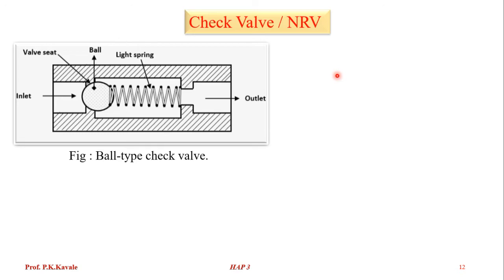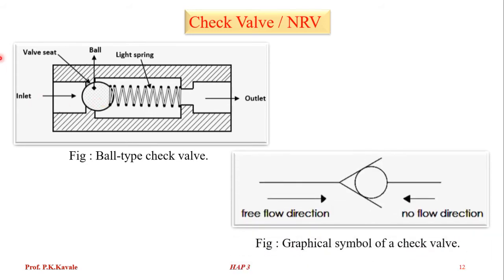The check valve is also known as a non-return valve. The valve body is hollow in shape — a cylinder — with an inlet port and an exhaust port. These ports are restricted by a ball element operated by a spring. The ball blocks the passage. When fluid comes under pressure, it overcomes the spring tension, pushes the ball, and fluid flows from left-hand side to the right-hand side. It does not allow reverse flow.